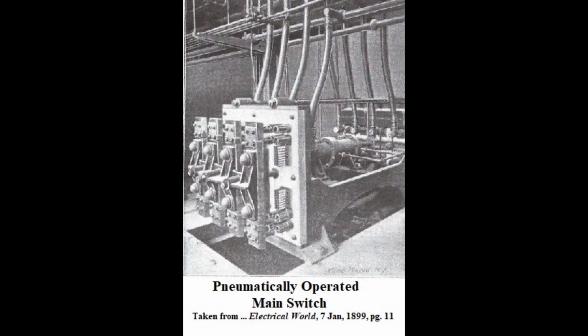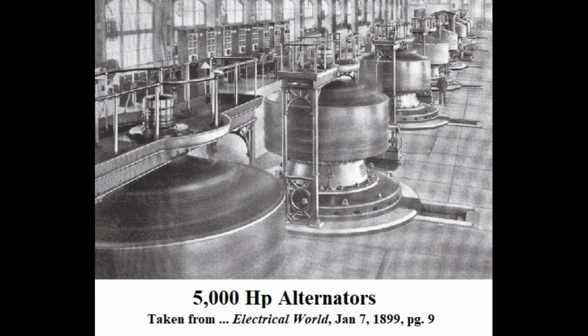The switch lacked any isolation between phase poles that would reduce the danger of phase-to-phase faults within the switch itself. So, the situation was that by the mid-1890s, the Adams Plant No. 1, with its 5,000 horsepower, 2,300 volt alternators, the limit of the air brake switch had already been reached. It was not suitable for circuit protection. In other words, the Adams Plant, the largest in the world at that time, had nothing that we would recognize in 2026 as short-circuit protection.